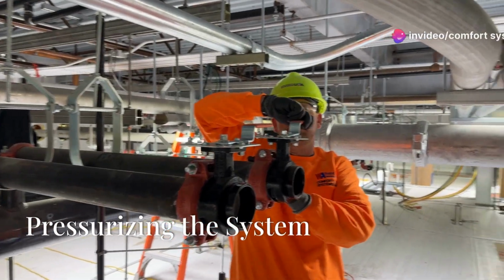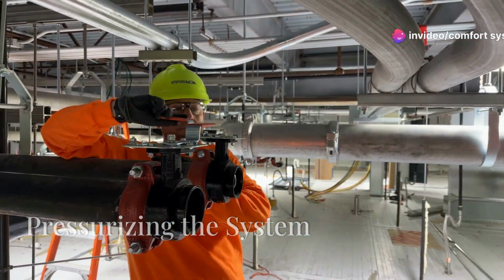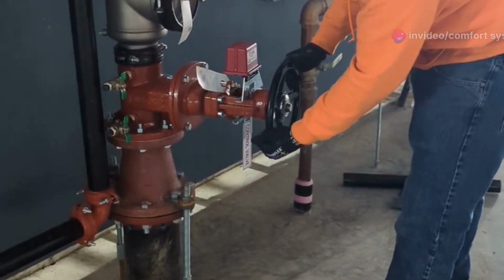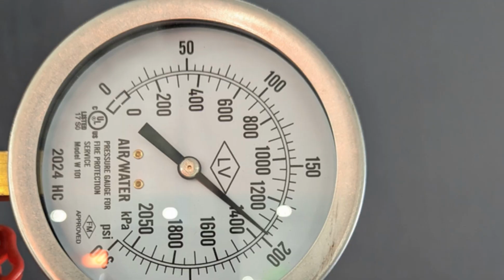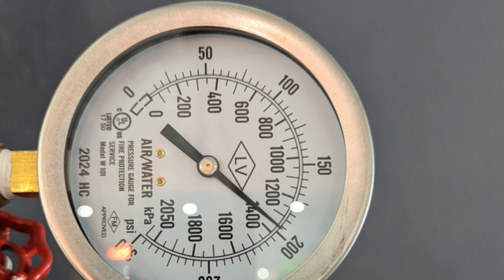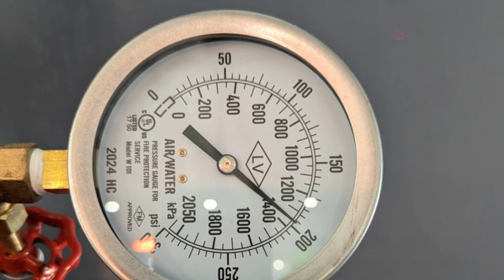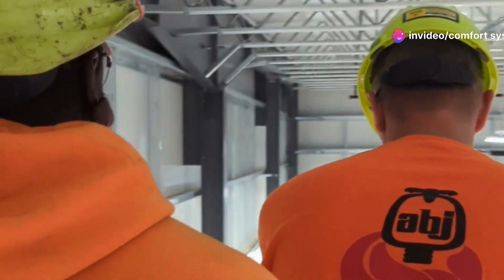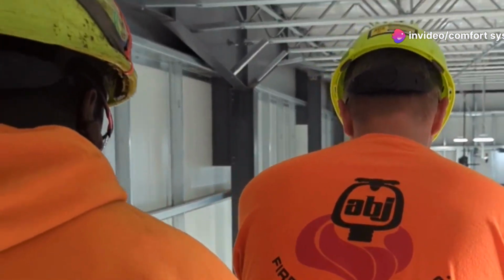Step 5. Begin pressurizing the system. Raise the pressure gradually until no more than 1/2 of the intended pressure is achieved. This pressure shall be held for a minimum of 10 minutes to allow the location of any major leaks. A walk-around inspection of the system is required prior to moving forward with further steps.